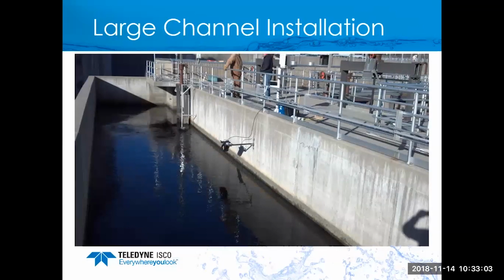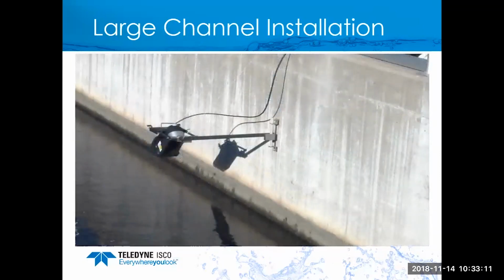So here's one that was a large channel where they're trying to measure that flow. The laser is not going to see the entire width of that, but the flow is fairly uniform, so they were okay with mounting it how they did. This really is a nice looking application, a nice looking installation. They mounted a U-channel bracket or an L-shaped channel bracket coming out to the side. They have a stainless steel support cable on the back to help keep it from vibrating around. So this might give you some ideas when you look at how you're going to install one of these. This is really what you need to do. But again, the XY axis on the laser is going to tell you if you're installed correctly or not.